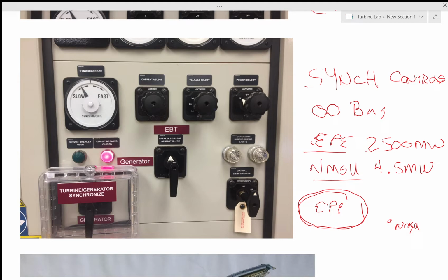Our turbine actually has an automatic synchronizer. When the waveforms, frequency, and everything else get into sync, it will automatically close our turbine breaker onto the El Paso Electric system, or close the EBT tiebreaker into the El Paso system, depending on how we're operating it.